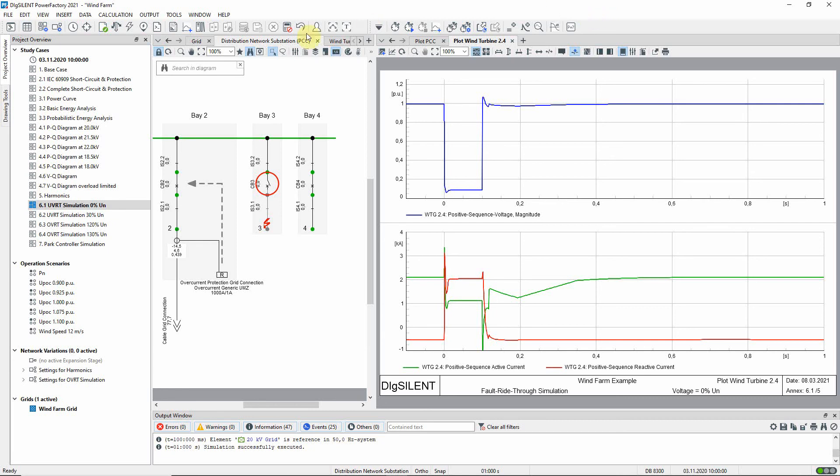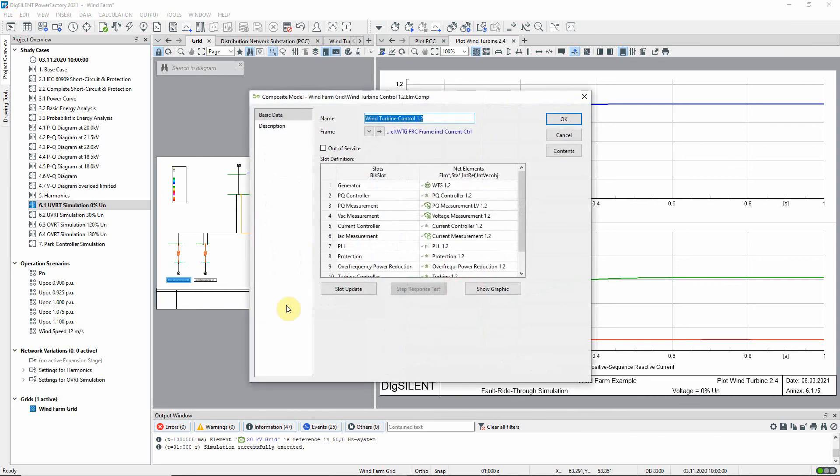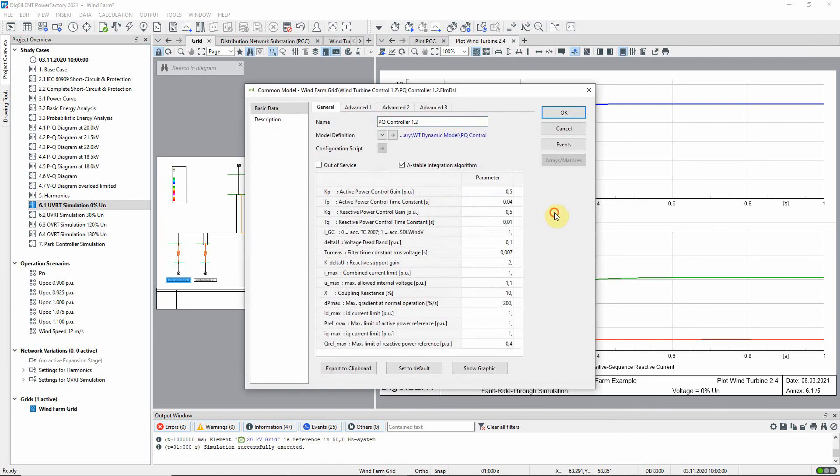Returning to the grid, and looking at a wind turbine controller model again, it is possible to see the parameters which control the fault ride through behavior of the turbine. For instance, the K factor which is the gain for the additional reactive current required for voltage support, is set to 2. This can be edited as required.